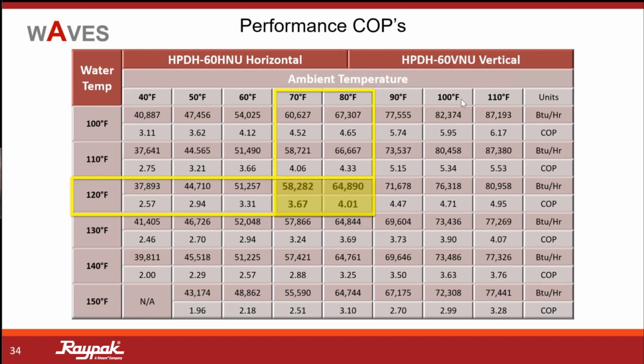135s coupled with this. And now you're going to start to see where we can start to shine in commercial applications, because we're banking on that stored water volume. We might have a dump load, but then have the rest of the day to harvest and recoup those BTUs. So as it pertains to applications, we really want to focus in on your specific region. What is that supply water temperature? What is your ambient air temperature? And again, maybe looking at these minimums here and what that production number would do. Does that make sense to everybody?